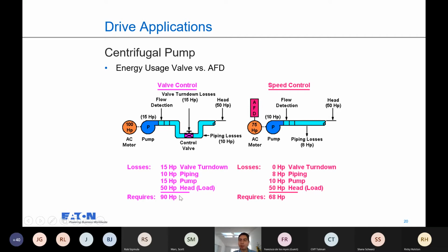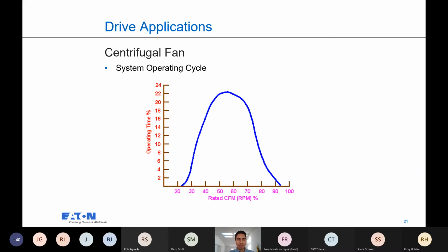Now let's compare that to maybe using an adjustable frequency drive. You reduce the piping, you reduce the horsepower of the machine, and then obviously you do not have the loss that you had through the turn down on the valve. That is significant. You go from 100 horsepower to 75 horsepower. So what I mentioned initially is because we do have many critical systems, we can use this as redundancy. So you can have a PLC control using both methods. You can have your adjustable frequency flow and just reduce the valve for energy savings. And then you can have your emergency or bypass operation with valve control. So good thought there. Let's continue on here.